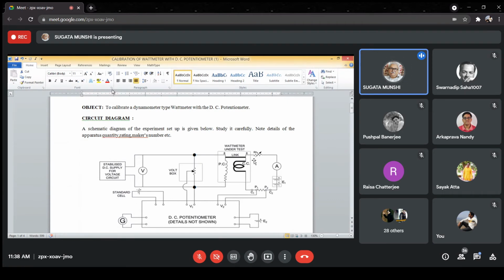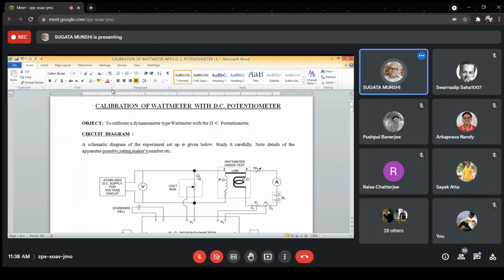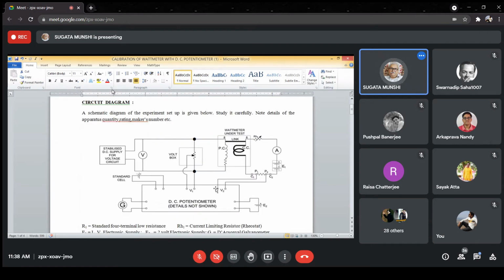So what is the procedure? First, connect the voltage sources, go to the experimental setup, and without turning on any supply, check whether the wattmeter is reading 0 watt. If it is not, there is a zero-adjustment screw on the casing of the wattmeter that must be adjusted to bring the pointer to the 0 watt mark. This ensures there is no error of the wattmeter at 0 watt reading—the percentage error is enforced to be 0.